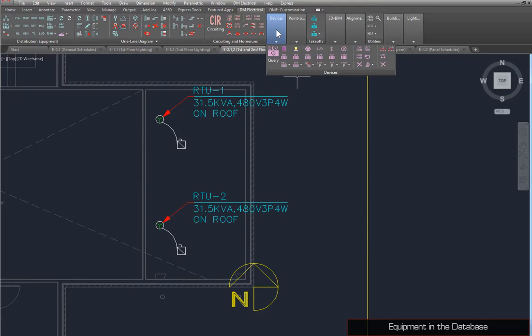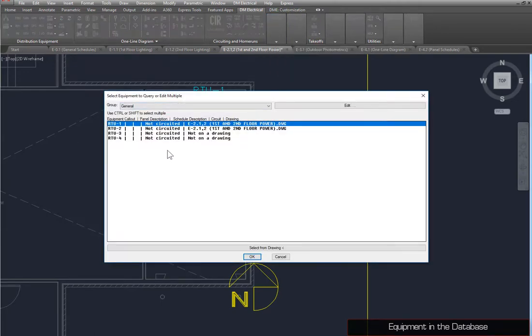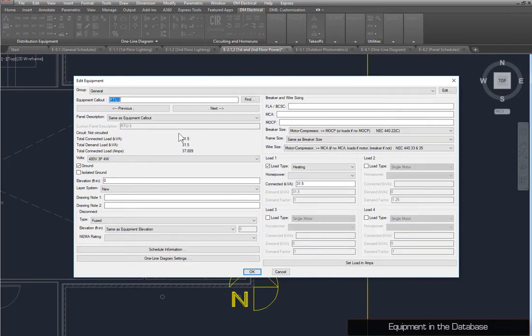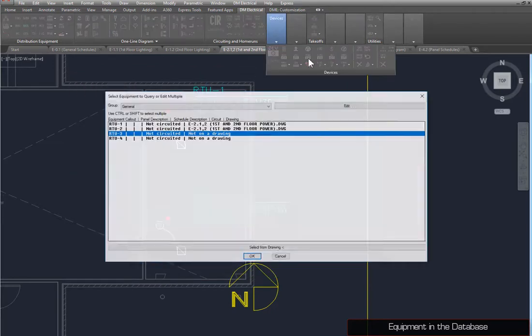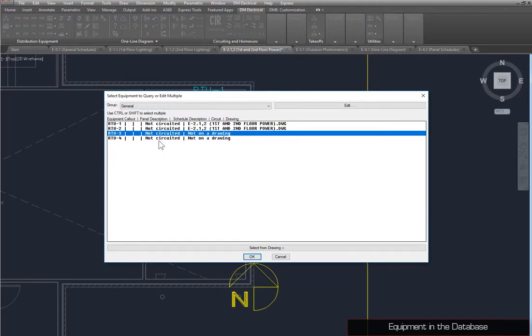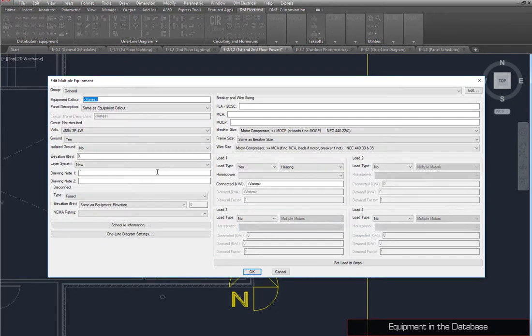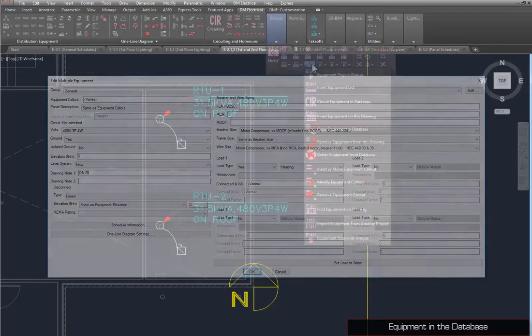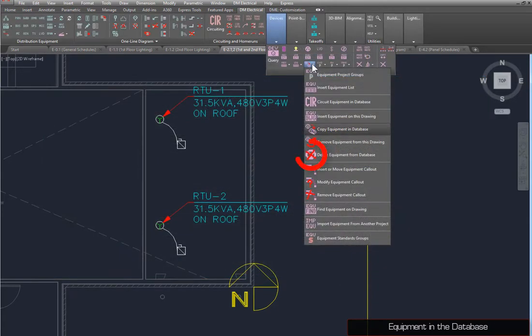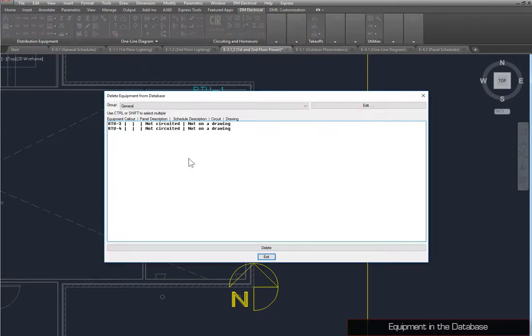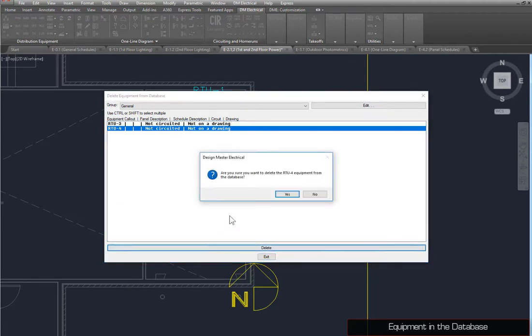Equipment in the database must be queried using the Query or Edit Multiple Equipment command. Query RTU3 and change the Connected Load to 25. Run the command again, select RTU3 and 4, and set Drawing Note 1 to On Roof. To remove equipment from the database, use the Delete Equipment from Database command. To avoid accidentally deleting database entries for equipment on the drawing, only equipment that has not been inserted on a drawing will be shown. Select RTU4, press the Delete button, and confirm the deletion.